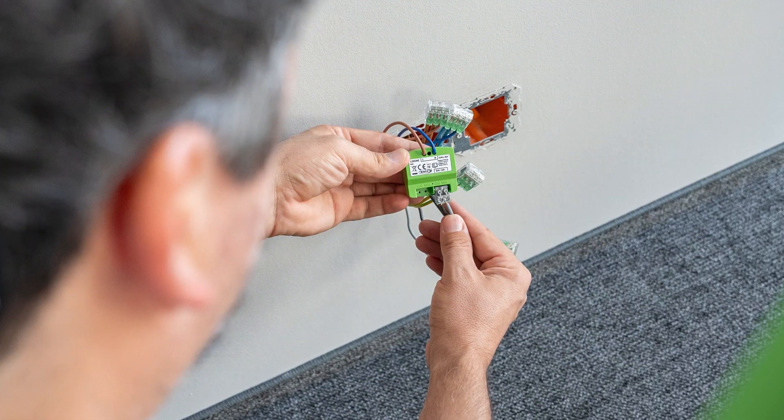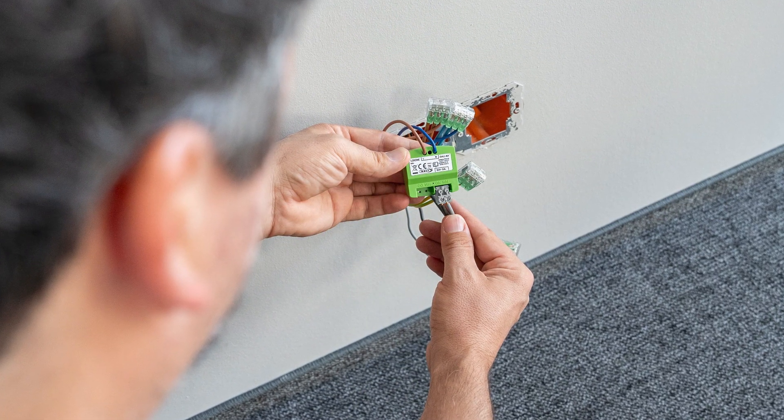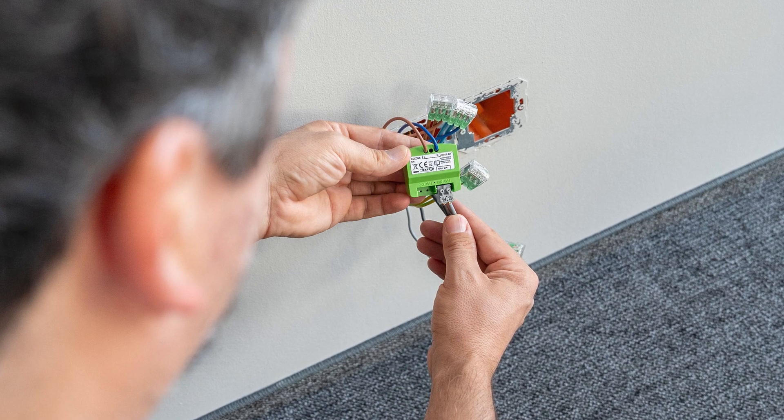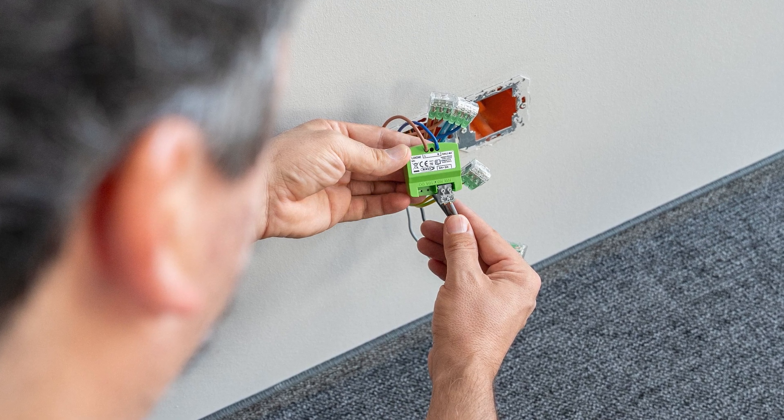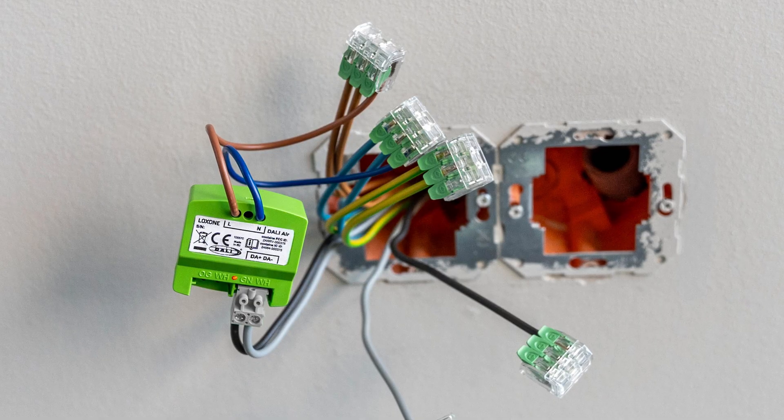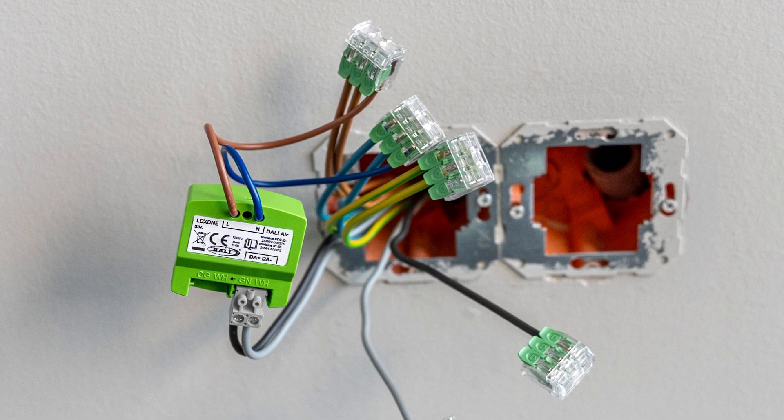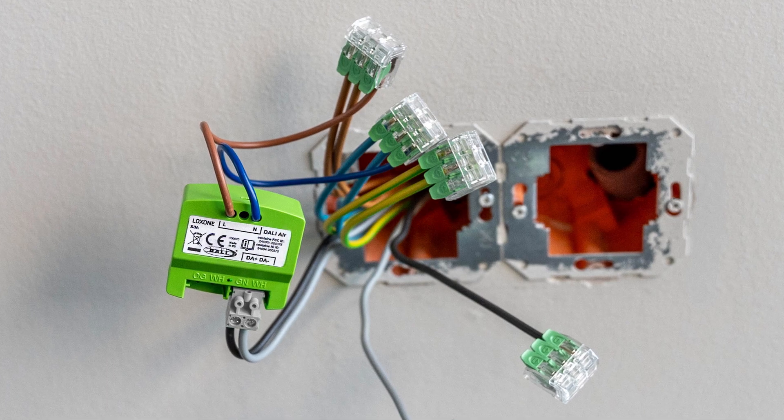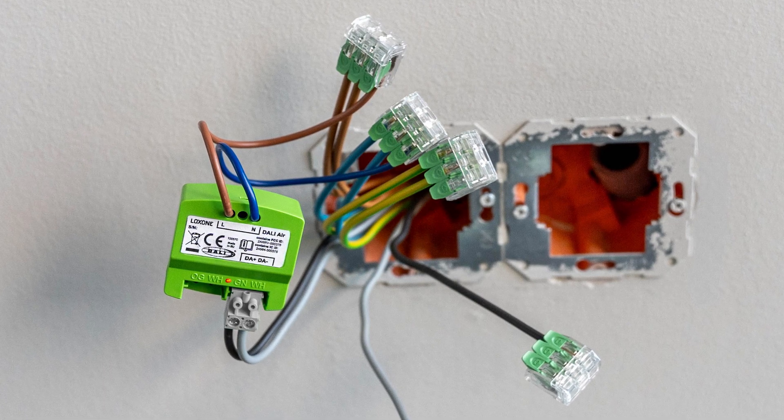But now let's look at the commissioning using the Loxone config. If the DALI Air is supplied with the operating voltage 230 volts and is in the delivery state, the commissioning mode is automatically activated. This is signaled by the red, green, orange flashing LED on the device and can now be found in the search dialog.